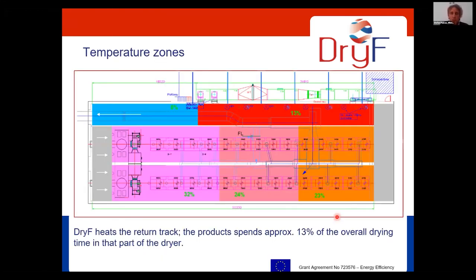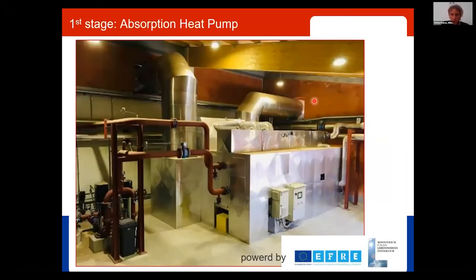When you have a bird view on the dryer, this is a four track dryer where the product spends most of the time at ambient temperatures of maximum 90 degrees. And on the return track, this is the last track here above, we can do the final drying. So the product spends about 13% of its drying time in this hot section. And this is the dry efficiency section. A duct was bolted on the building with a fan and a heat exchanger supplied from the dry efficiency heat pump. And here we can provide higher temperatures to do the residual drying.